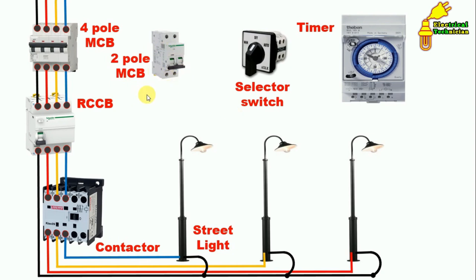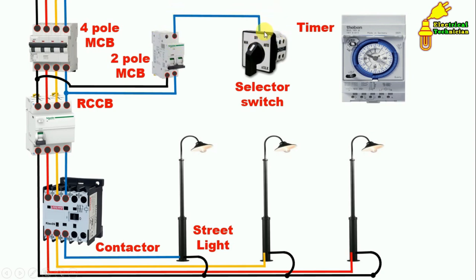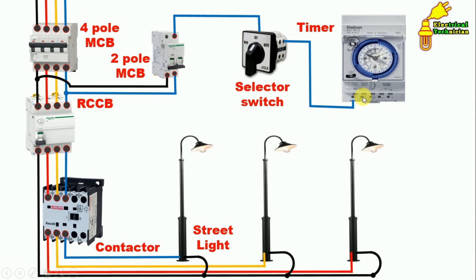For control wiring, first provide input power supply to the control MCB — connect a wire for phase supply and a wire from the neutral terminal. From the outgoing terminal of the MCB, connect a wire to the common terminal of the selector switch. Put the selector switch in auto position, and from the terminal where we get continuity, connect a wire to the NO contact or common terminal of the timer.